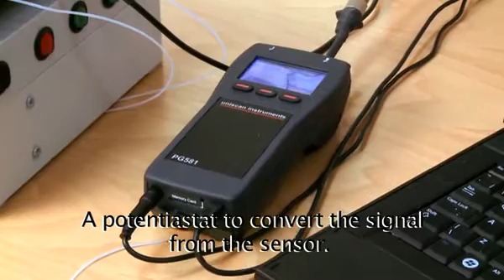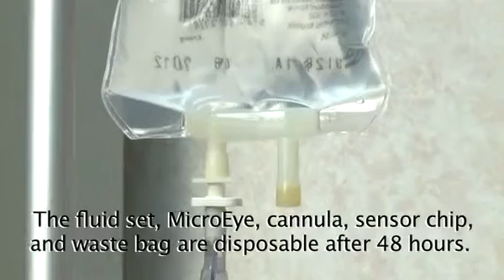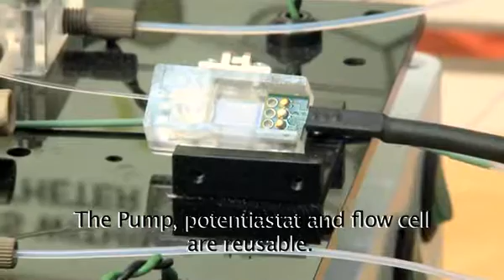A potentiostat to convert the signal from the sensor. A connector, which may be wireless, to a monitor or laptop. We use a laptop for demonstrations, but a PDA works well, as does a connection to a bedhead monitor. The fluid set, MicroEye, cannula, sensor chip and waste bag are disposable after 48 hours. The pump, potentiostat and flow cell are reusable.